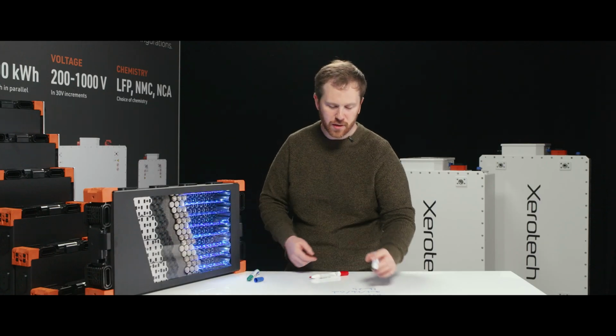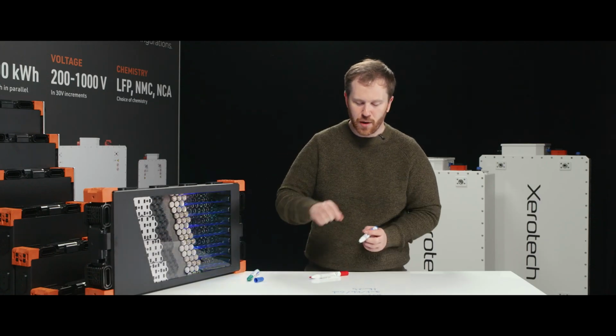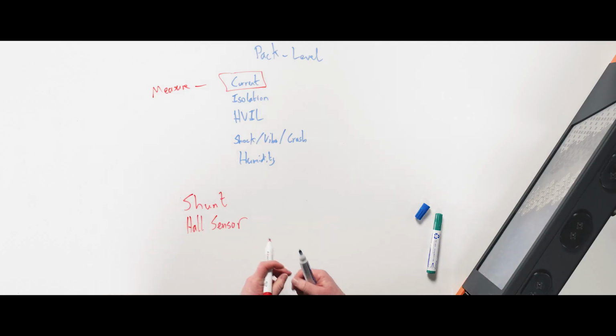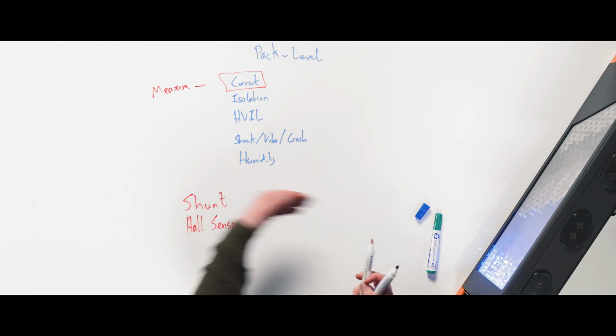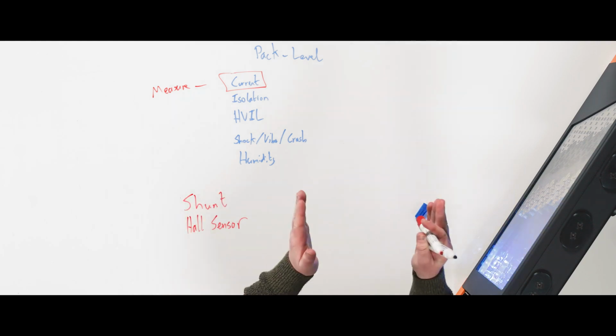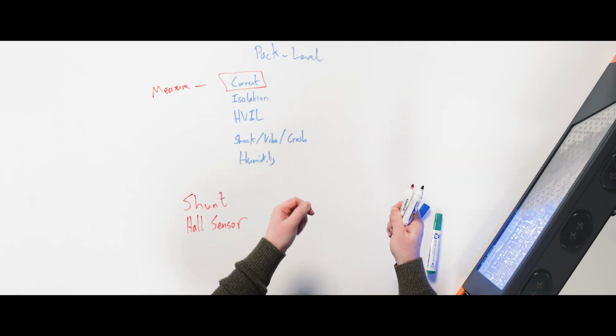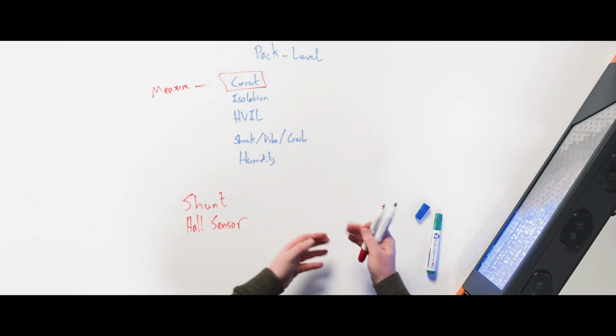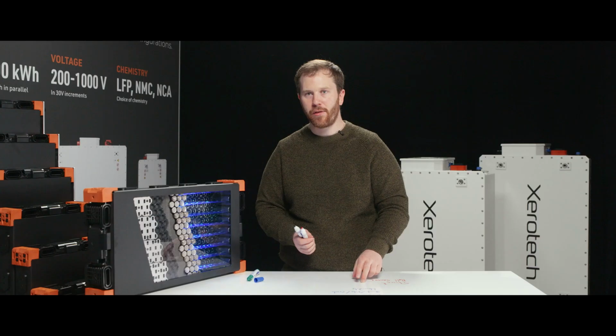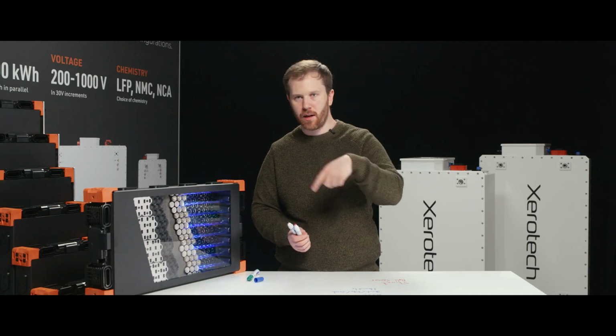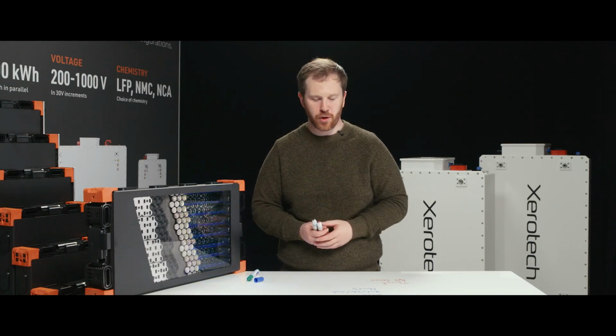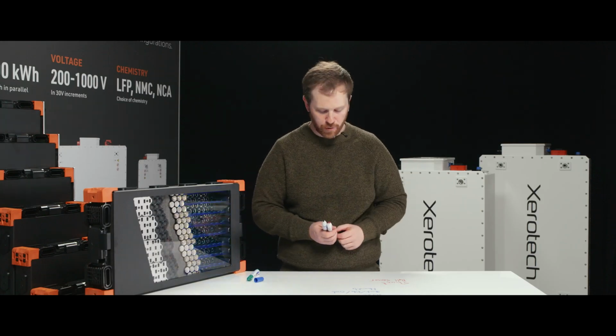So the way we do this in most systems is we're measuring this number of different ways. It could be with a shunt or a Hall sensor. A shunt is basically a lump of copper that we pass current through, and there's a little bit of a voltage drop on it. So you measure the voltage drop with a known resistance, and it tells you the current. Or with a Hall sensor, you pass current through a magnetic loop and it generates a voltage that you can measure and infer the current from.